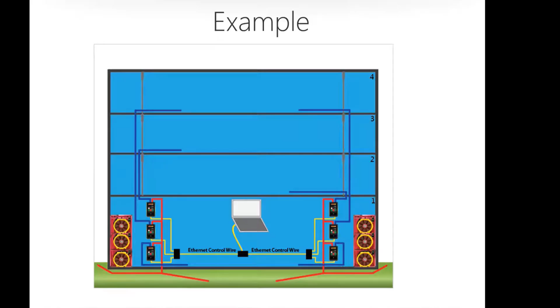So we had 4 different test stations. Aaron, can you see this okay, this test setup? Yeah, this is coming through. We had 4 fan groups at 1 test station: 18 fans set up in the loading bay area, 9 in the main entrance, and 2 groups of 3 on the roof. That gave us pretty good coverage to get that building under our desired pressure.